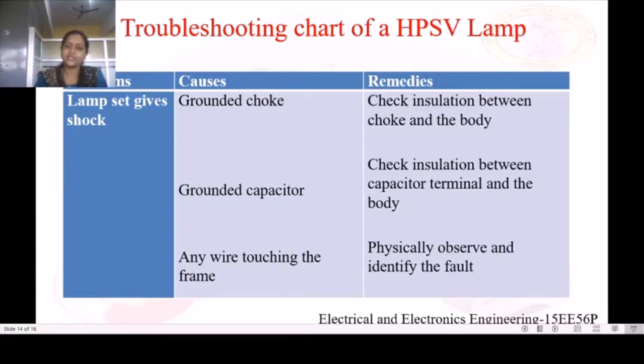For this, we need to physically observe for any loose connection in the wiring, or we can also identify this fault by using a series test lamp by checking the continuity, or we can conduct a ground fault test to see whether the wire is touching the frame or not using a series test lamp. If the series test lamp is in off condition, then we say that there is no loose connection or no wire touching the frame or body of the high pressure sodium vapor lamp set. So this is about troubleshooting of high pressure sodium vapor lamp set.